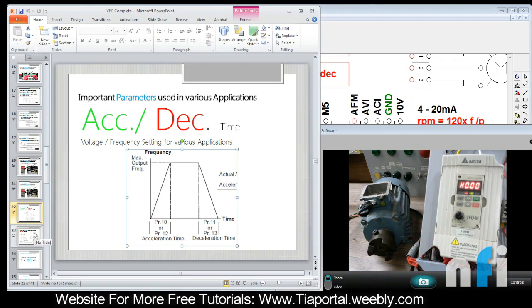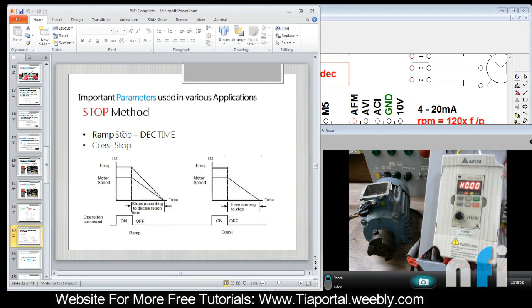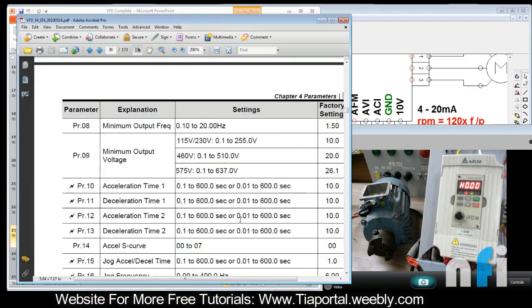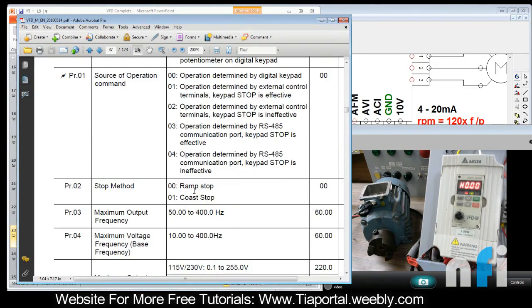And there is one more parameter associated with that, which is ramp stop, stop method, which says how you want to stop your motor. By default, it is at ramp stop. If you want to see that, it comes in the parameter 02, stop method, it's ramp stop by default.